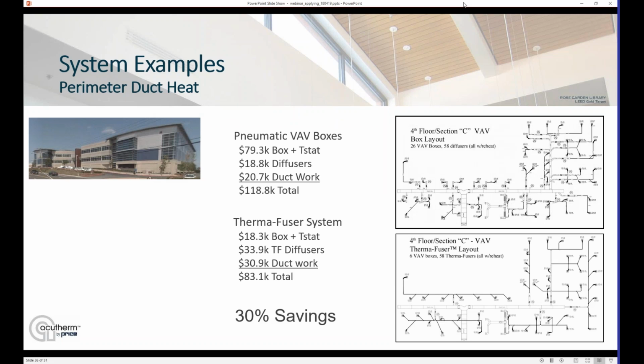Also, there can be a very cost advantage to go with a Therma-Fuser diffuser system. A lot of people have an idea that the VAV diffuser costs more than an old fixed diffuser, and that's true. But when you get into the system installed costs, it's the VAV boxes that are the majority of the cost in the system, not the diffusers or the ductwork. So in that previous example, by reducing the number of VAV boxes to just what we needed for pressure control and to provide the reheat when necessary, we can really get some good savings out of this job. In this particular one, it was a 30% reduction in cost.